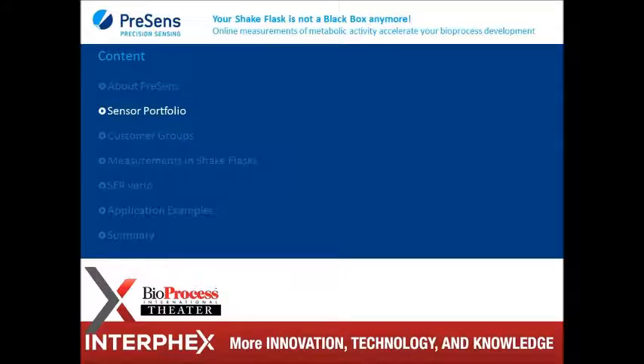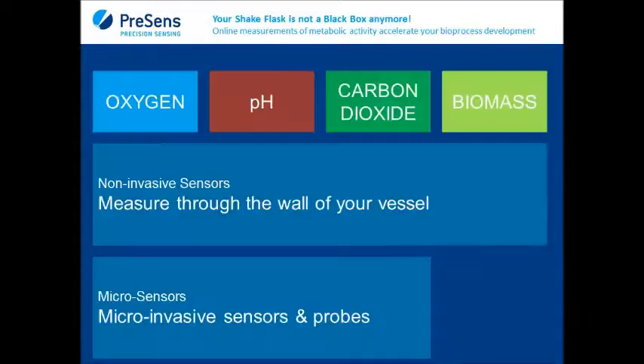I'd like to continue with a brief rundown on our sensor portfolio. So we have sensors for oxygen, pH, carbon dioxide, and biomass. The key feature of our technology is that it's a non-invasive technology, so you can measure through the wall of your vessel. It's all optical. These are all optical sensors, so there's no physical contact between the actual sensor probe and the transmitter. Only the sensor probe, which is a fluorescent membrane, has to be in contact with the media or the solution that you want to measure. The format of the sensors can be what we call mini sensors, that would be a range from 2 millimeters up to a few centimeters, or micro probes that go down to a size of 20 micron.